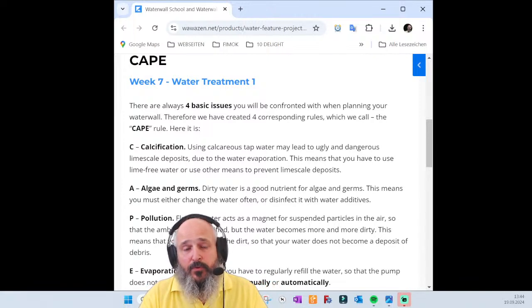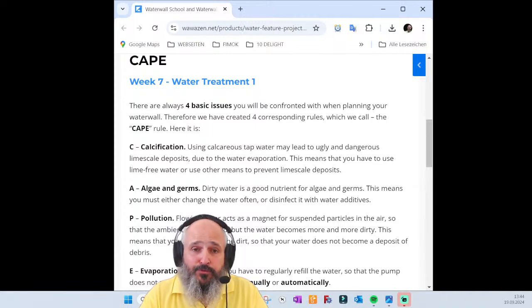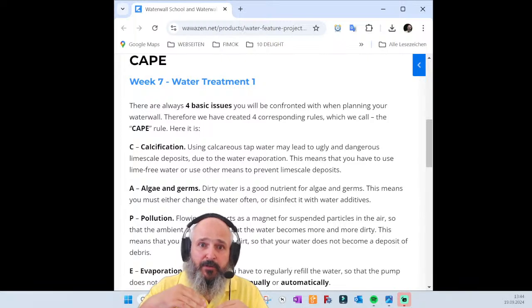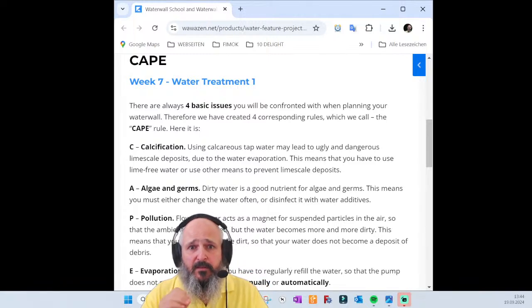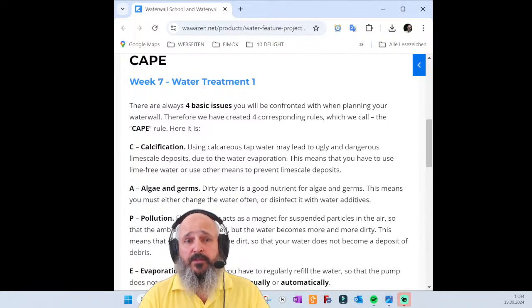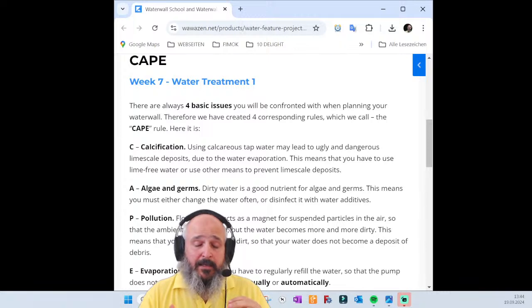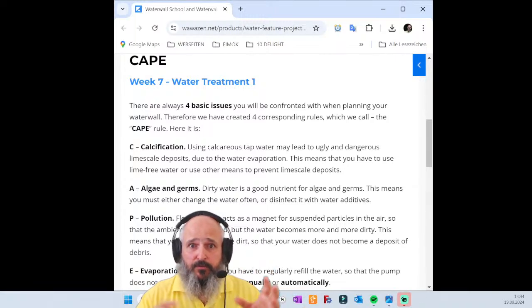And the other way, of course, which most of my customers choose, is an automated refilling system, which means there is a swimming valve inside your system and the water level is permanently kept at the same height. Very important is that if you do so, you have some safety measures. If your swimming valve fails, then you would have non-stop refilling and your system would create water damage.